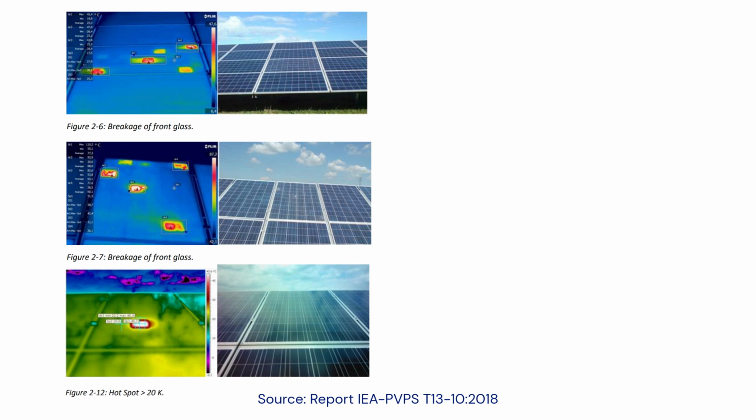For reliable results, infrared images should be taken under high solar irradiance, above 600 Watt per m², and under stable ambient conditions, for example with no clouds, low wind speed, and a stable ambient temperature. It is also essential to know the technical details of the solar array, such as module inclination, orientation, string configuration, and variations within the generator, in order to properly evaluate the infrared images.